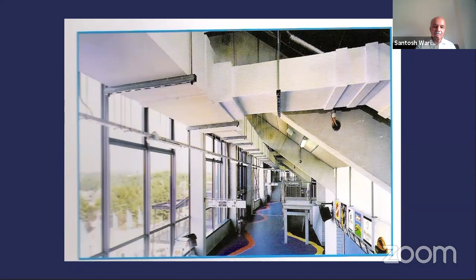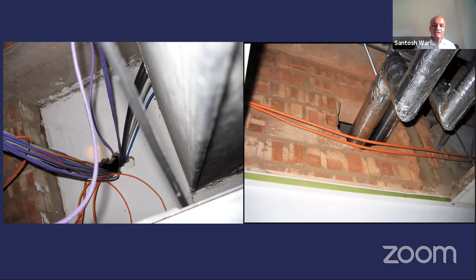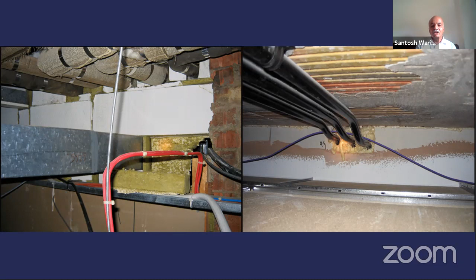So these are some examples of the normal situation without any compartmentalization, of how the penetration is done. There is no sealant used, no fire barriers are used, and haphazardly cables and services are passed from one compartment to another. Here again glass panes are used, but they are not properly sealed. A number of services, air conditioning ducts, electrical cables, fiber optic cables, are passing as they are with the holes. If anything goes wrong, definitely they will pass heat and smoke. They have spent money on the passive fire protection system, but the workmanship is very poor, so it is of no use. Definitely in case of fire, the heat and smoke will pass from one compartment to another.